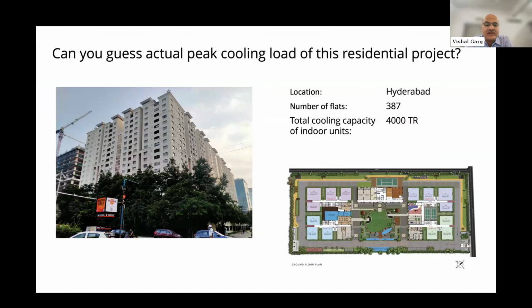This is the picture of that project. It has about 400 flats. The total cooling capacity of indoor units is 4,000 tons. So if I aggregate all this and put a central chiller to supply to all the indoor units being 4,000 tons, what would be the peak load or the size of the chiller?